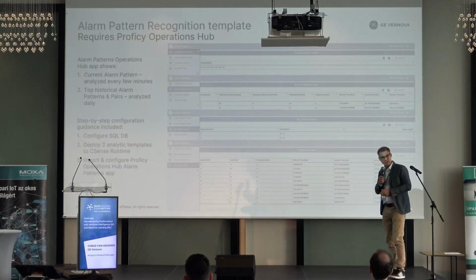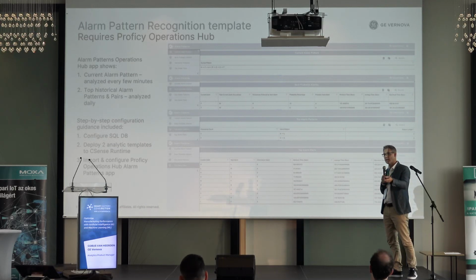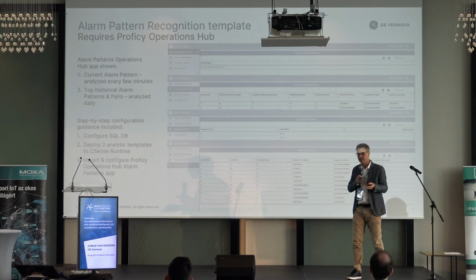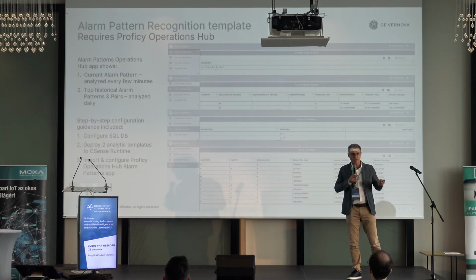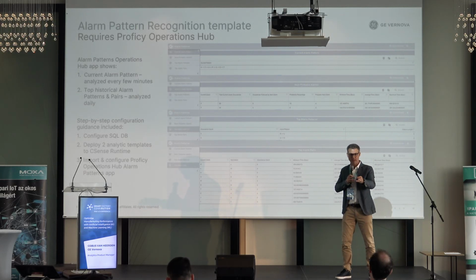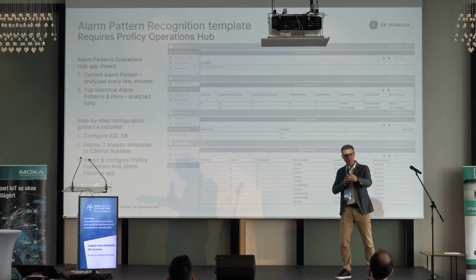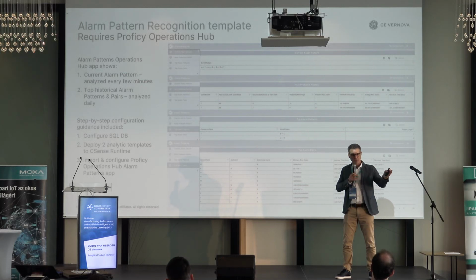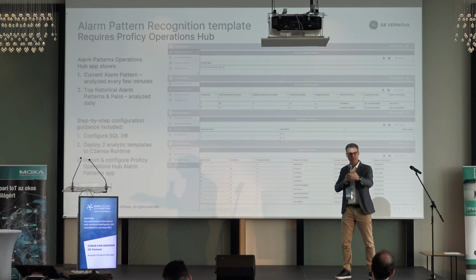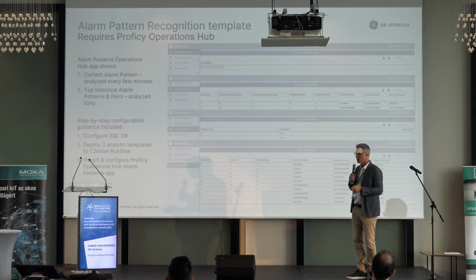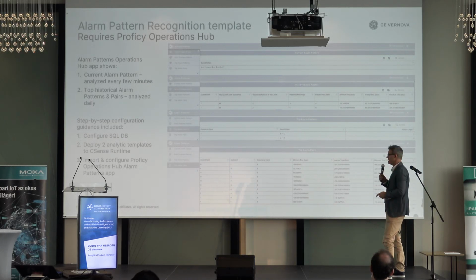So alarm pattern recognition. Your SCADA produces alarms. But what we're hearing from our customers is, maybe there's a burst of alarms. Or if I have a long alarm history, can I learn something from the sequence of events in which alarms typically occur? Or the root cause. When alarm A happens, it's always followed by alarm B, typically 30 seconds or a minute later, and this happens all the time. Or when there's a certain burst of alarms, you get a certain pattern of 3 alarms that always repeats, always follows one another. That is the sort of insight that this template will allow you to unlock.